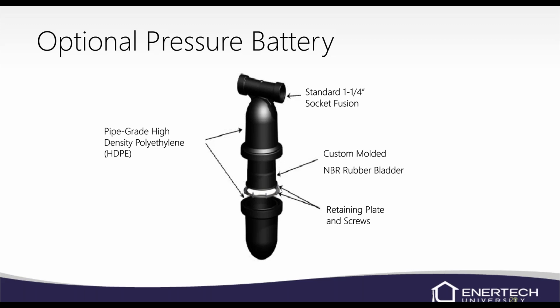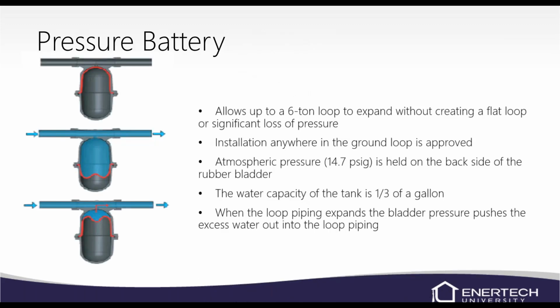It's got basically a rubber bladder inside of there and some retaining screws. It's not really field serviceable, so if something were to happen to it, you can't fix it in the field. But basically, the pressure battery allows up to a 6-ton loop to expand without creating a flat loop or significant loss in pressure.